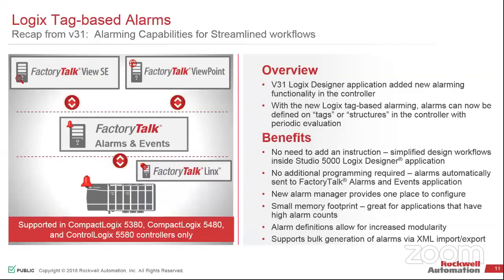And then you can still use essentially the HMI alarm events tag structure. At that point, we're looking at 10,000 alarms. You're pulling from the HMI at that point. You're not pushing from the controller, but everything that we do from a PlantPAx side, so all of the process library objects, are using that style of HMI alarm. You can have all three on one system. The operators won't know where they're coming from. So just as you look at what you're doing, those are the kind of use cases. If you have questions, just let us know.